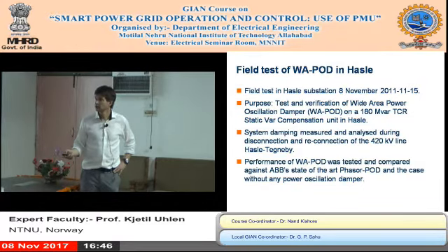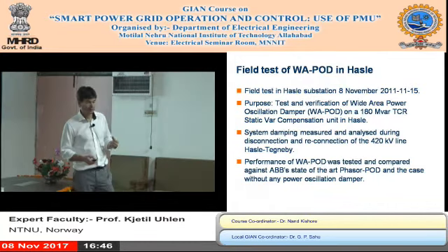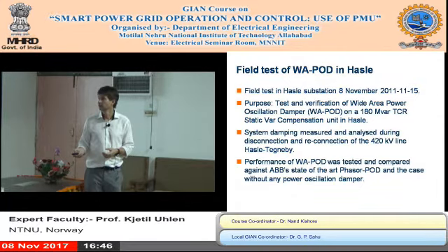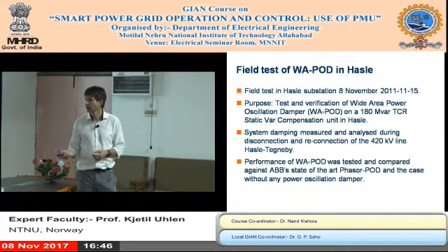We excited the system by disconnecting and reconnecting lines close to the site, and we compared the performance against the conventional, state-of-the-art power oscillation damper that ABB manufactured, and without any POD.